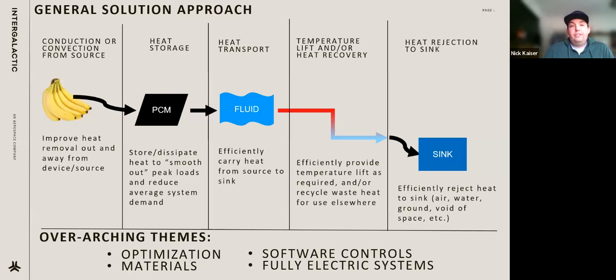Another one—and it's kind of funny because software is certainly not a new thing, embedded control—but this gets into problems more specific to aerospace, an industry that's slow to adopt things. Just by applying intelligent controls, we're able to really reduce power consumption in a lot of systems. A lot of legacy ECS solutions, for example, will run fans, compressors, and pumps at the same speed all the time, so the power draw is high all the time, when in reality max load is pretty infrequent. If you're able to use basic software controls, you can really reduce the amount of power draw on average.